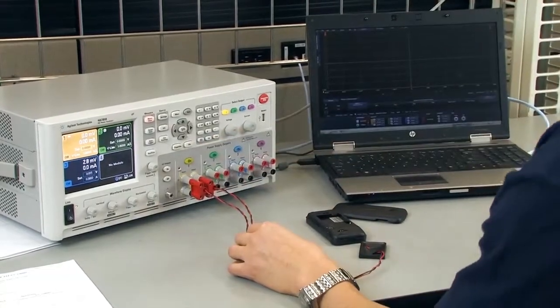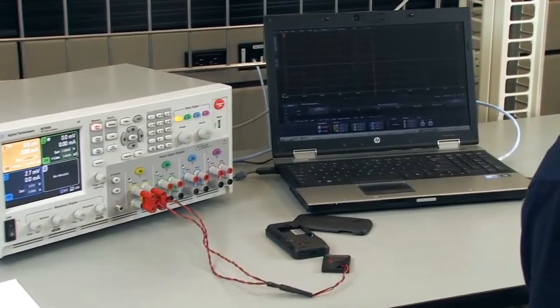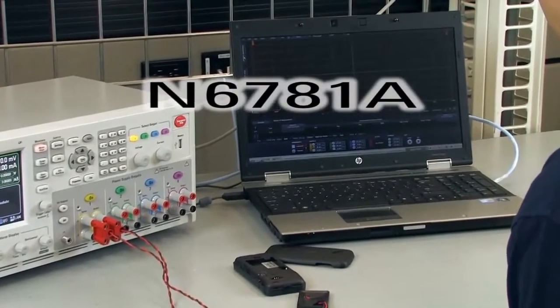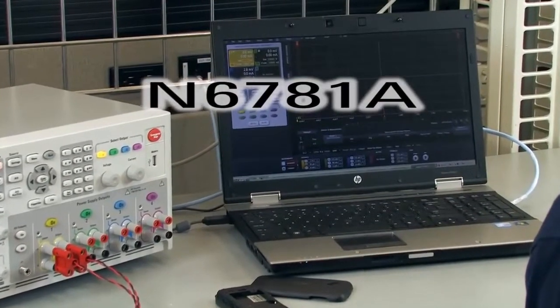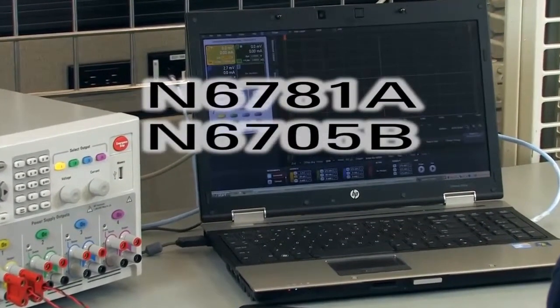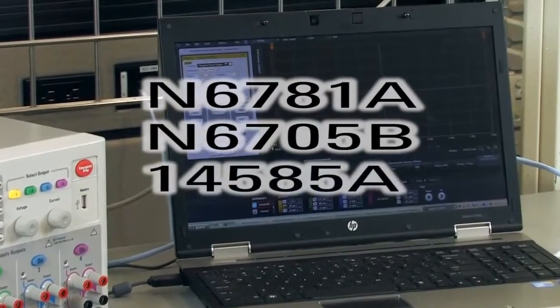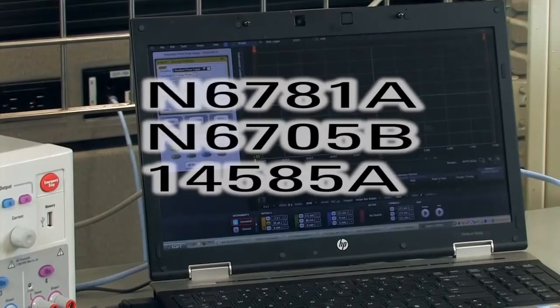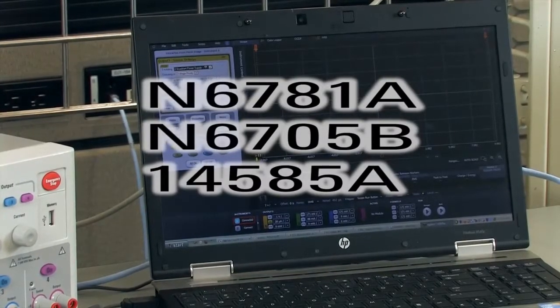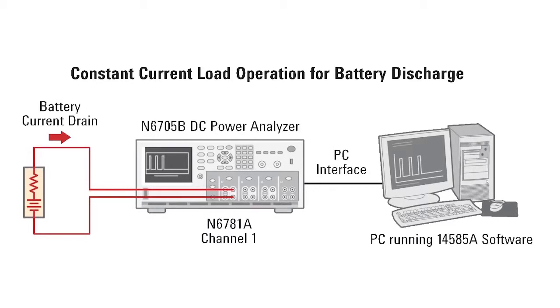Agilent Technologies has superior tools designed specifically for characterizing batteries. The N6781A source measure unit is tuned for battery testing. When combined with an Agilent N6705B mainframe and 14585A software, it is a superior solution for measuring and analyzing battery capacity and energy. We use the setup depicted here to discharge a rechargeable mobile phone lithium-ion battery at a fixed C rate. The full 2-quadrant capability on the Agilent N6781A source measure unit makes it well suited for use as a precision high-performance electronic load, as well as a precision DC source.